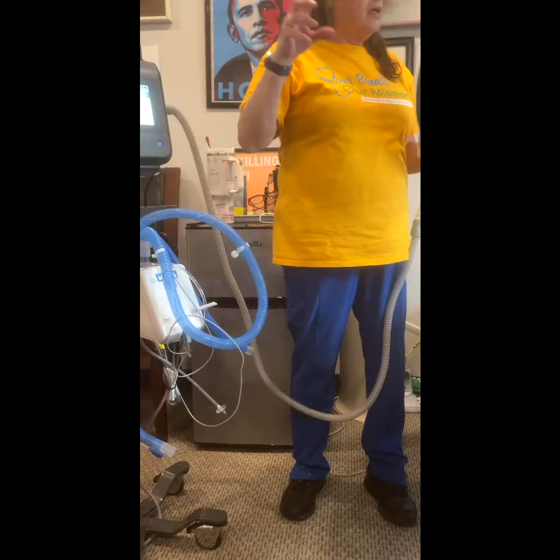And then we have apnea. The only good thing about this one is that apnea doesn't alarm if they're shallow breathing, only if they quit breathing. That was one of the good things about it. Whereas with the Trilogy and the Evo, you don't even set those alarms because they will start alarming if they're shallow breathing, if they're riding the vent. So like this patient right here, Allison is riding the vent, unless I do this where I'm breathing for her.